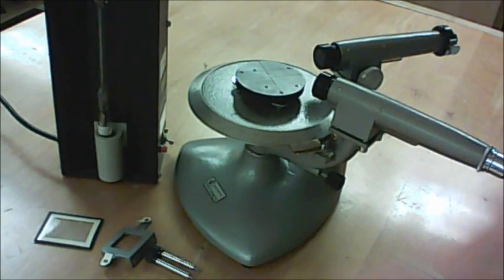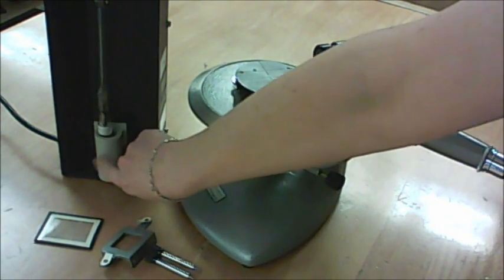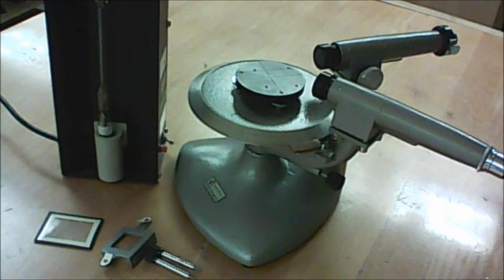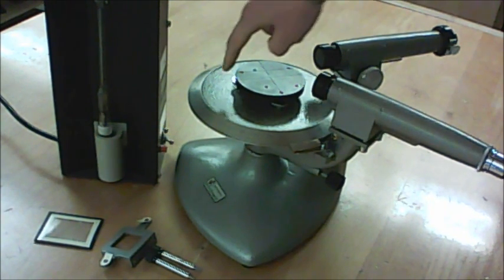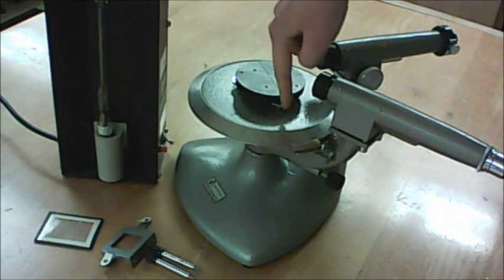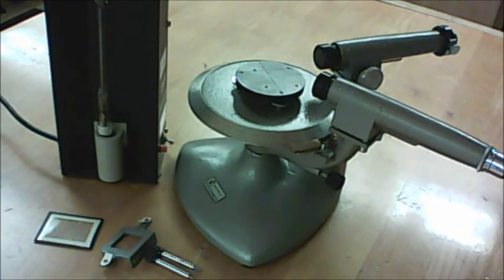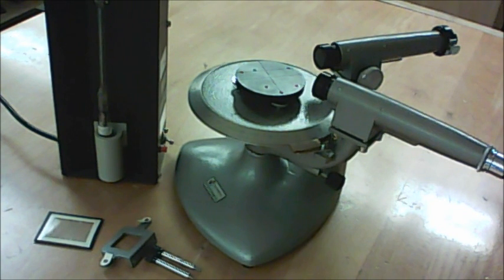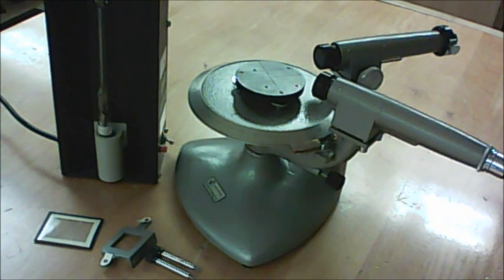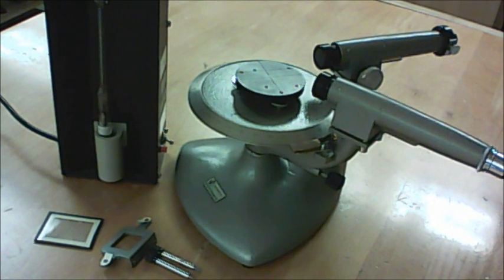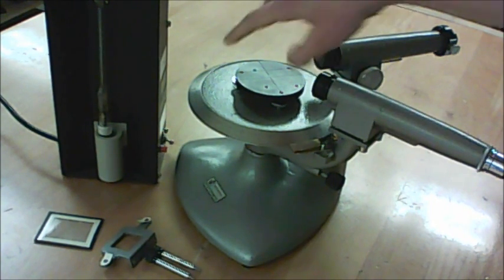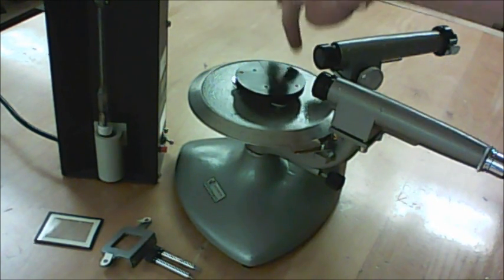Another thing to be wary of is that these are very high voltage, so keep your fingers away from the sockets. Another thing to be aware of is that there's these little leveling screws on the black table in the center of the spectrometer, and you should never touch those because it screws up the spectrometer in a way that's not easily fixed.